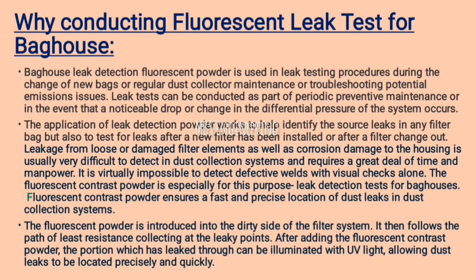The fluorescent contrast powder is especially suited for leak detection tests in bag houses. It ensures a fast and precise location of dust leaks in dust collection systems. The fluorescent powder is introduced into the dirty side of the filter system, where it follows the path of least resistance, collecting at the leaky points. After adding the fluorescent contrast powder, the portion which has leaked through can be illuminated with UV light, allowing dust leaks to be located precisely and quickly.